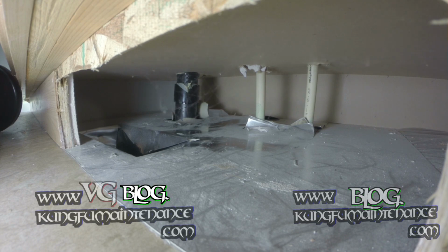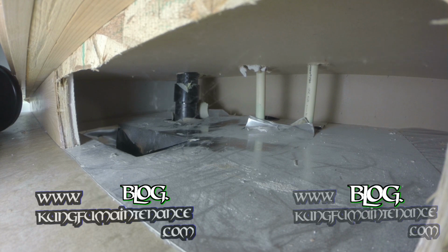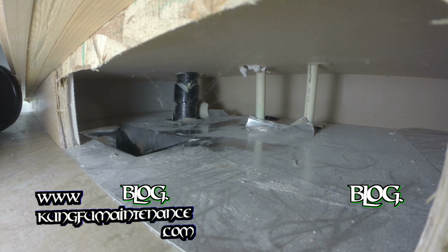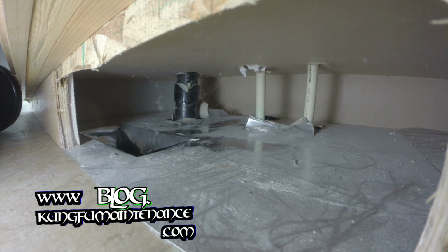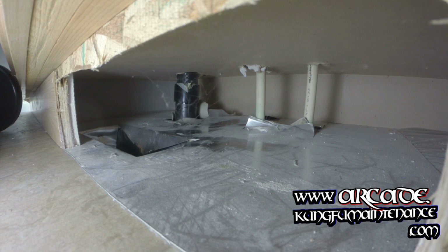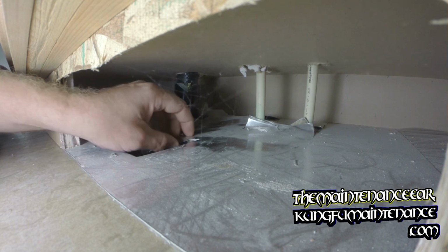There's going to be some piercings in the fabric skirt that's on the bottom underneath the house. Now what happens is we're losing airflow down into that space under the house, into the crawl space, and we're winding up cooling the crawl space. So this is one of the main inefficiencies for mobiles.